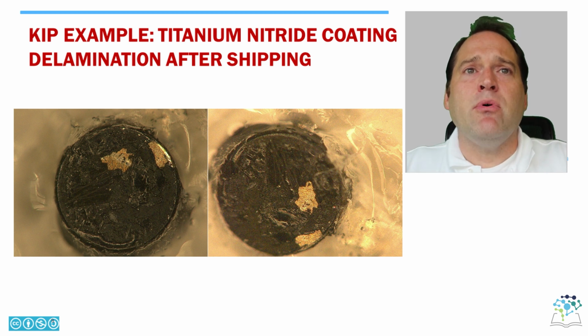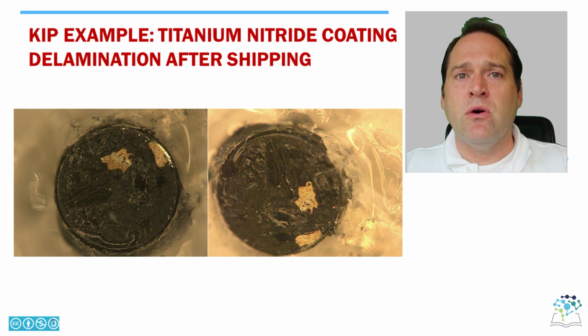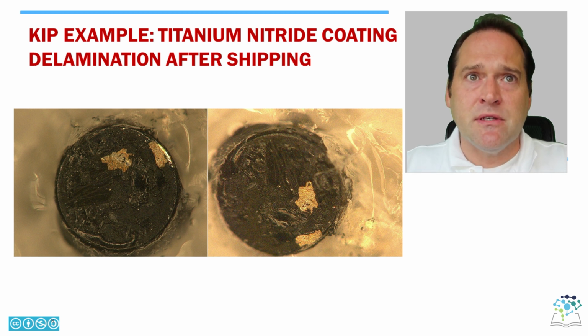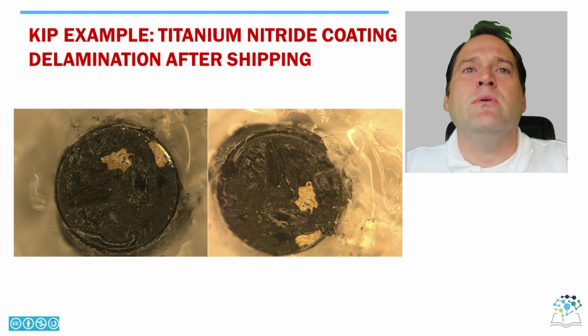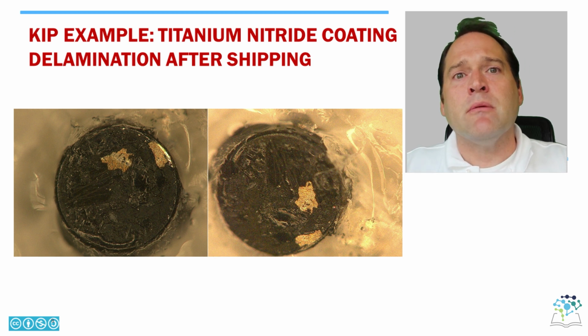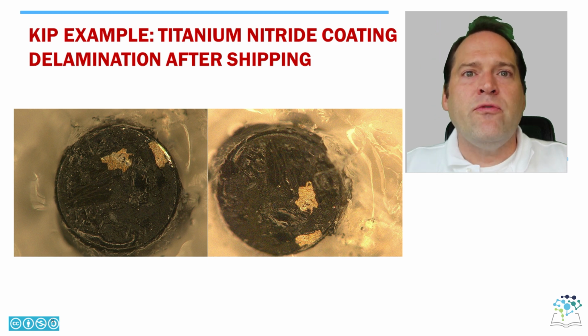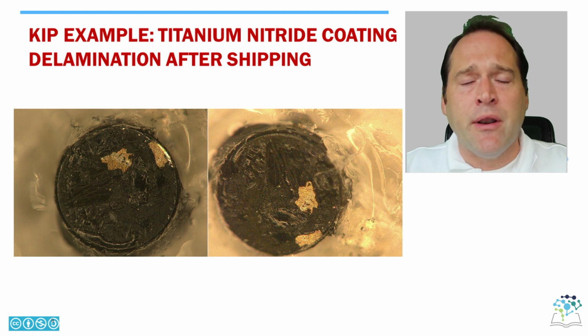So one illustrative example I like to use is a simple shipping issue. This is actually an electrode that I designed that's coated with titanium nitride. And I went through several coatings to attempt to improve the stimulation safety limits for these electrodes. What you'll note in the picture in front of you is that the coatings are imperfect. There's a couple of flaws in what is that black area, which is the coating, and under it is a platinum iridium electrode. Now these flaws weren't there when it was initially coated at the provider, but due to shipping and vibration during shipping and due to thermal cycling, some of the coating material that's supposed to help with the stimulation safety had actually fallen off.